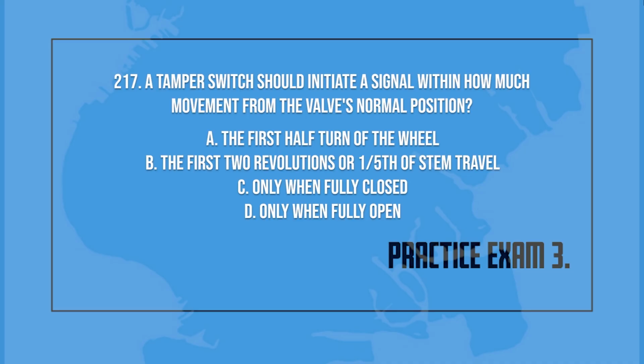(217) A tamper switch should initiate a signal within how much movement from the valve's normal position? A. The first half turn of the wheel. B. The first 2 revolutions, or 1/5 of stem travel. C. Only when fully closed. D. Only when fully open.